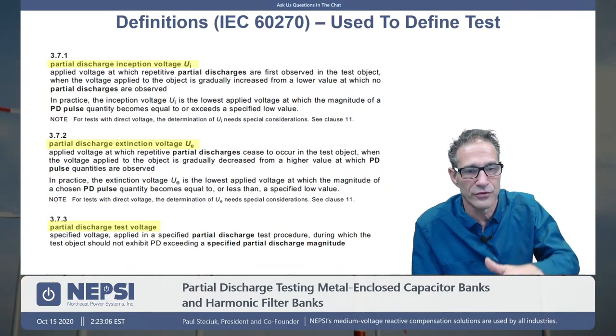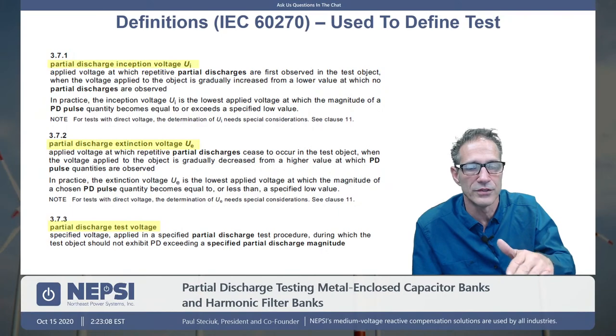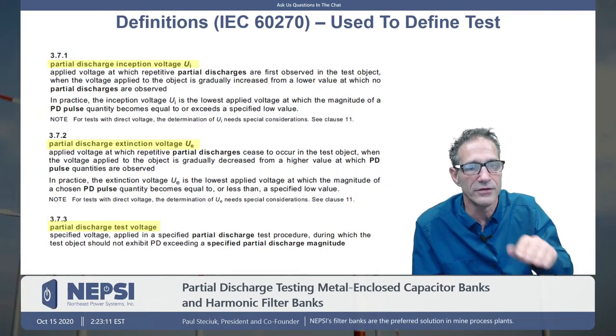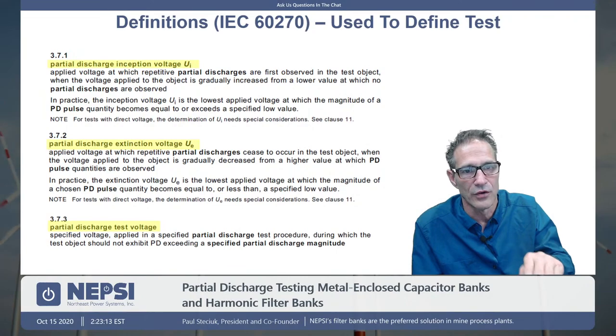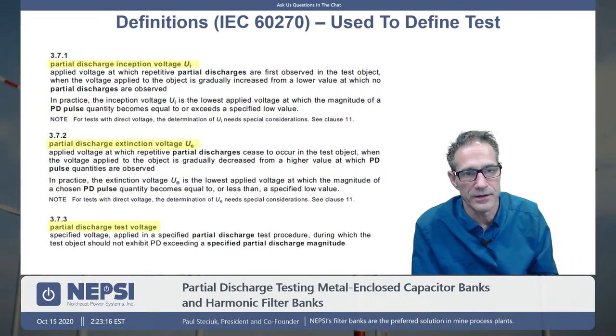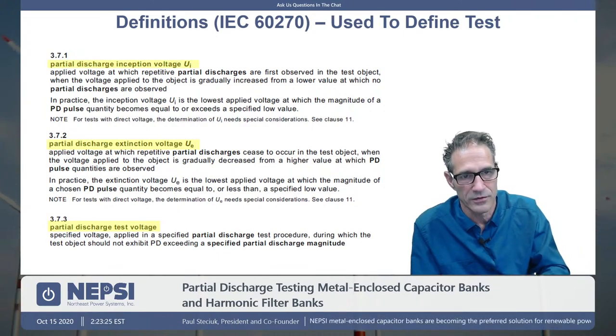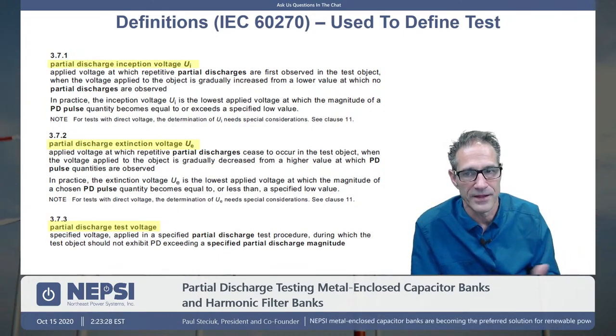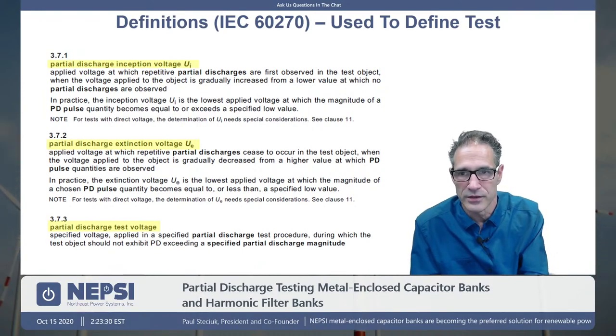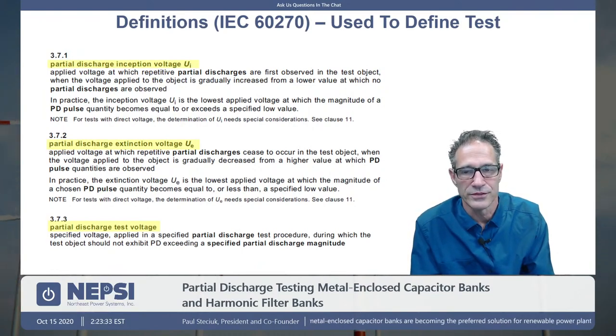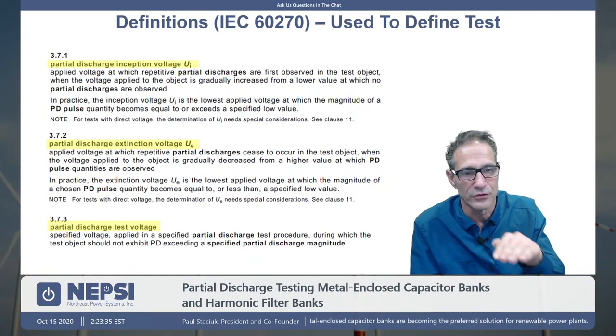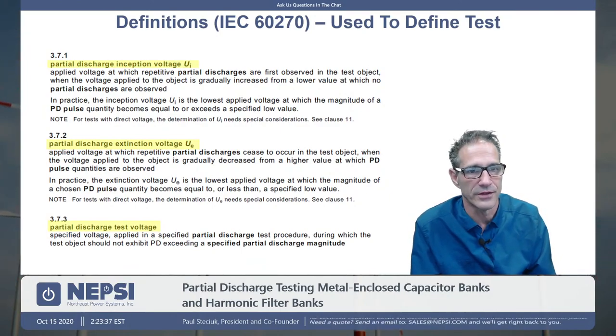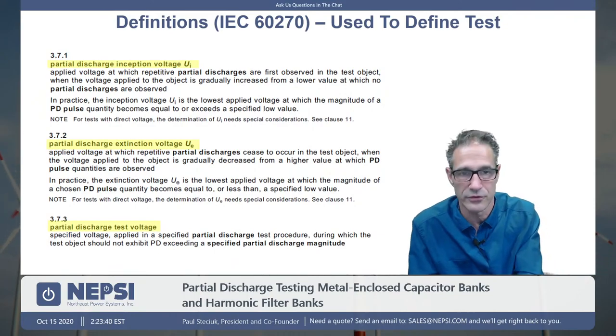At that point, the system would drop down. But if the system voltage dropped back down to 34.5 kV and I didn't drop below my extinction voltage, corona would then persist forever. And that's really what you're trying to make sure: if I do go into partial discharge because of an overvoltage condition, that when my voltage drops back down, I drop below that extinction voltage. And that's what this testing is about. And then we have this term, partial discharge test voltage, and that's really the test voltage or the passing voltage by which this extinction should occur. And those are the values that are written in the tables that I will show in a moment.